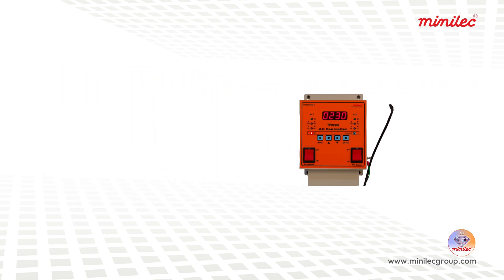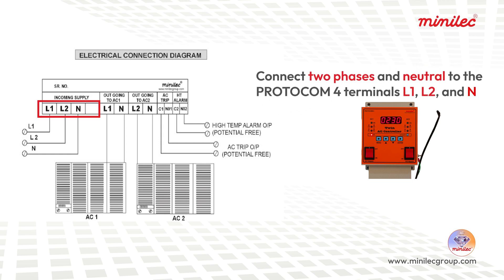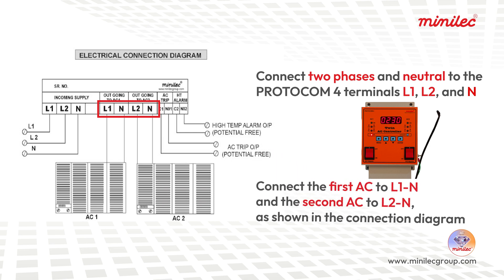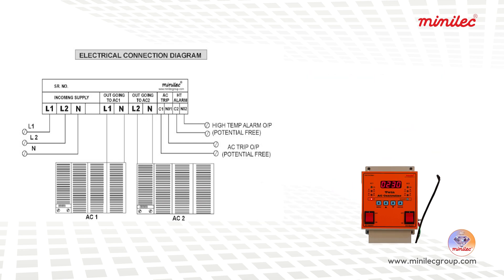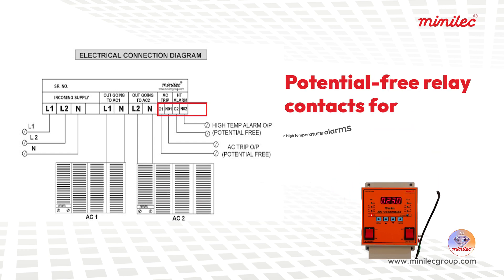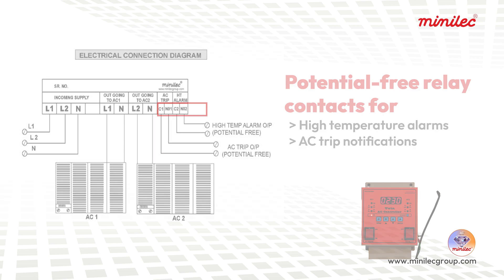To set up the device, connect two phases and neutral to the PROTOCOM 4 terminals L1, L2 and N respectively. Connect the first air conditioner to L1N and the second to L2N as shown in the connection diagram. Potential free relay output contacts are provided for high temperature alarms and AC trip notifications.